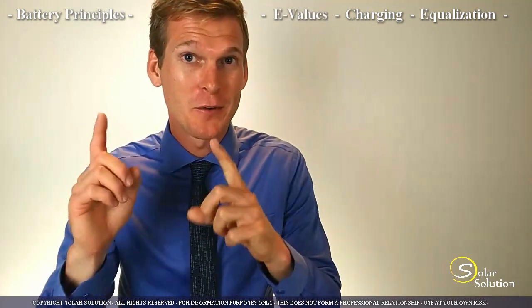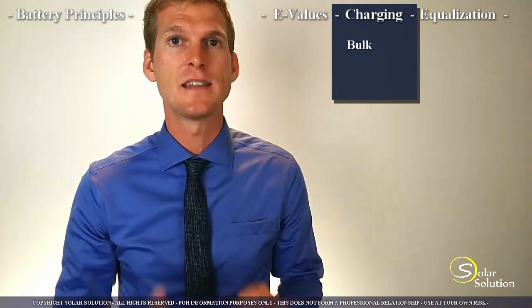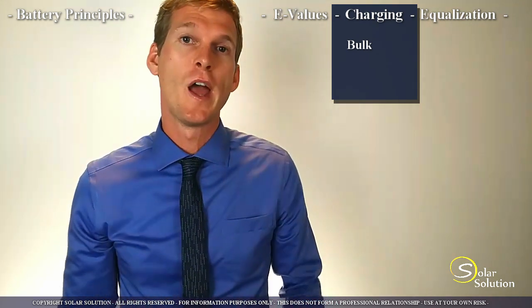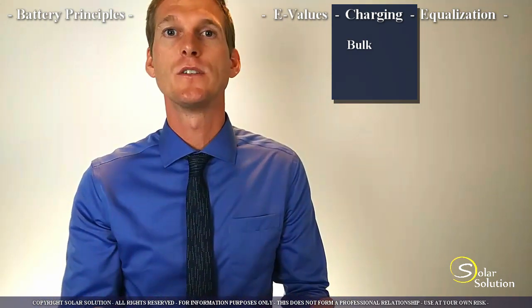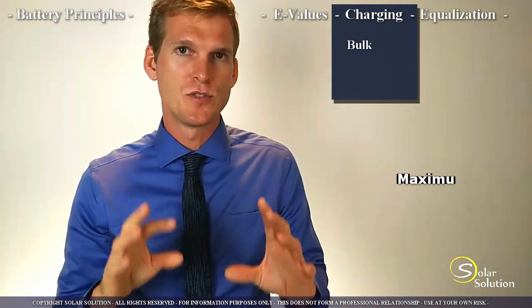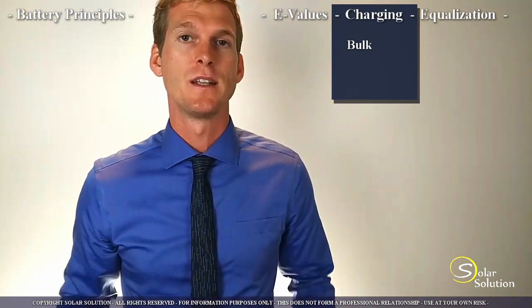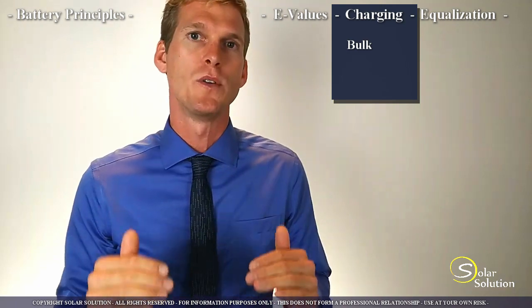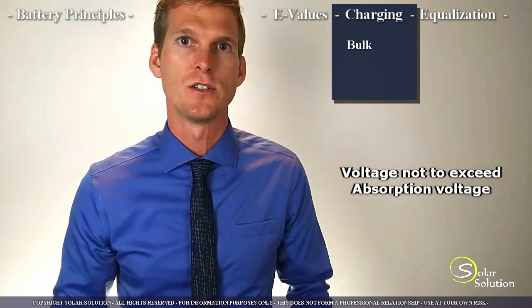Now that you're up to date with those two topics, we can look into the charging stages: bulk, absorption, and float. The first stage is bulk, in which the battery is typically less than 80% charged. In this stage we generally allow as much power to flow into the battery as possible, as long as we meet two conditions. First, the amperage flowing into the battery should typically not exceed 20% of the total amp hour rating. Second, as we push energy in, we don't want the battery voltage to go beyond a certain level — described as the absorption voltage — which is set in your charger devices.